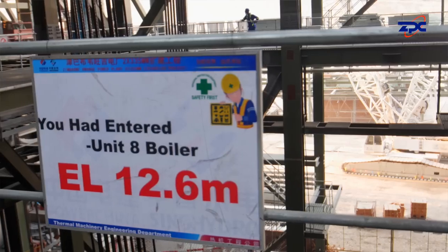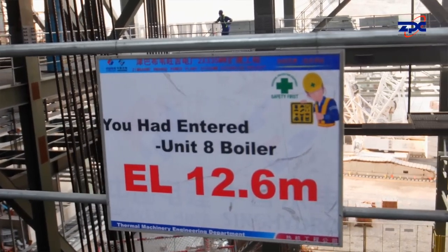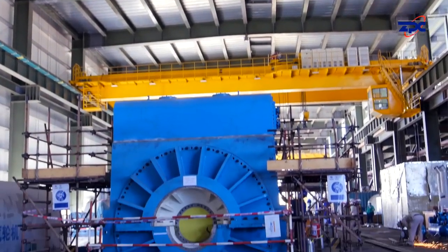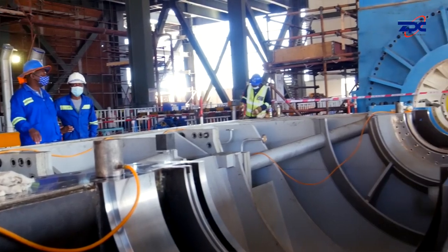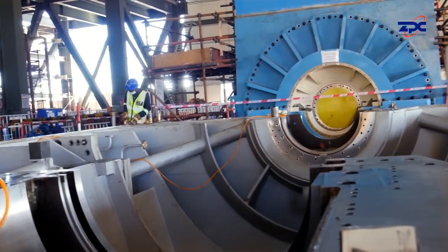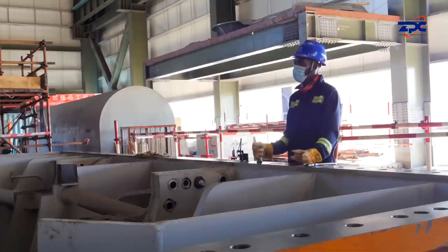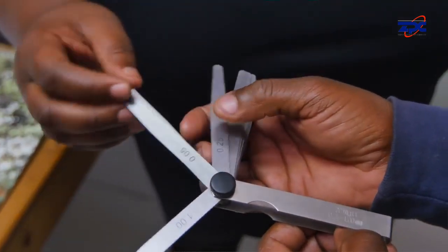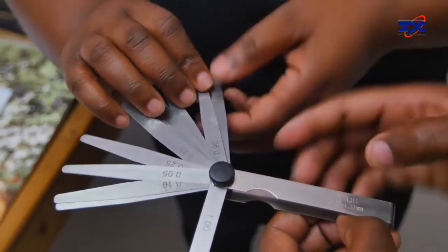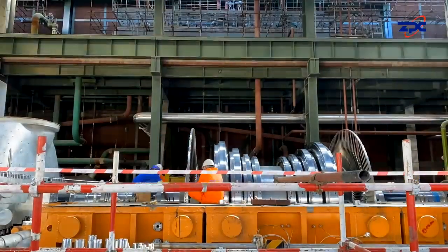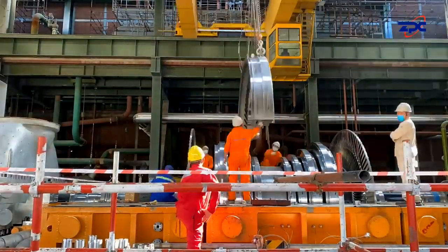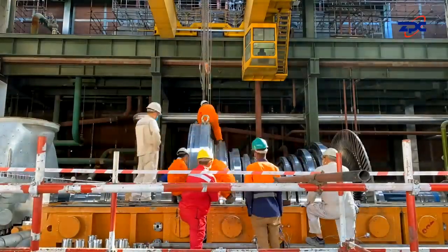The turbine is the one which is in between the processes. Currently we are on the 12.6 meter floor, the operating floor. For the Unit 7 turbine, we have the alignment of the LP lower outer casing with the soleplates. This is the preliminary alignment before we move on to the final alignment. The turbine is so delicate. We actually measure clearances in micrometers, so you would use what we call a feeler gauge. Miss any of that, and the moving parts and the non-moving parts will rub, and you have huge vibrations.